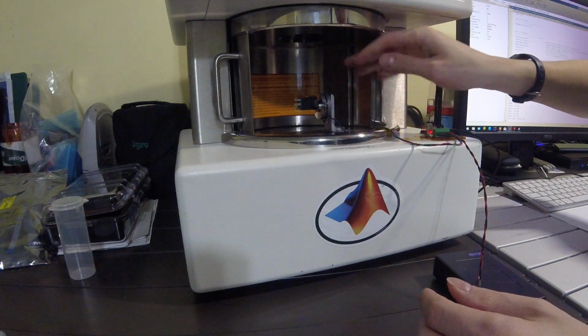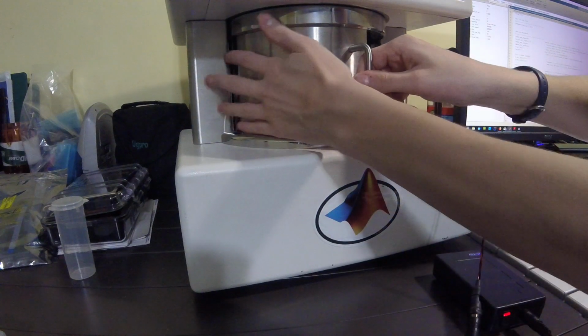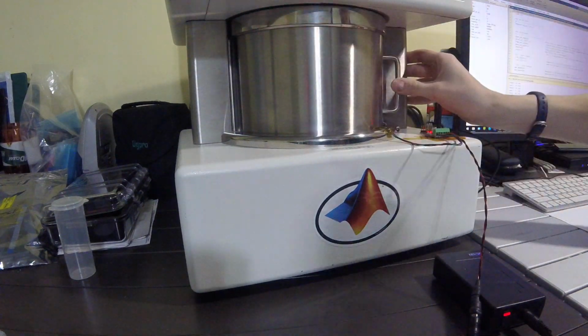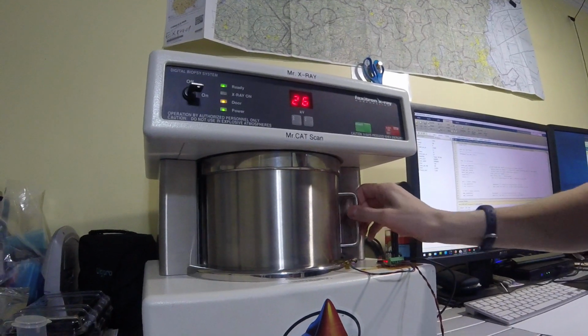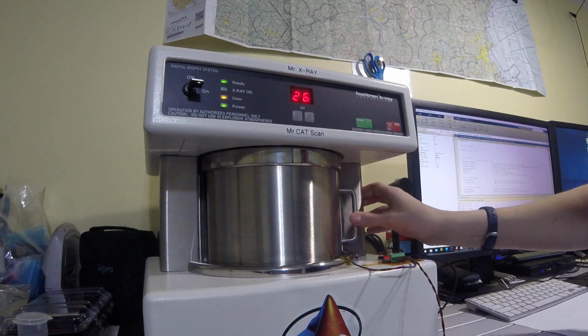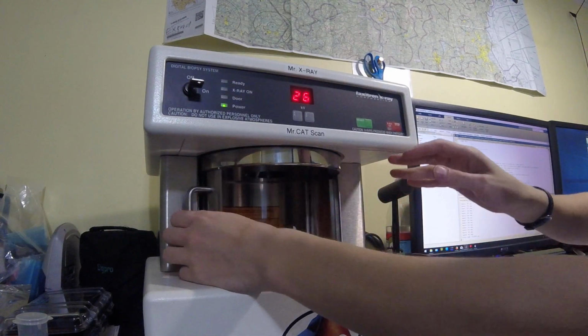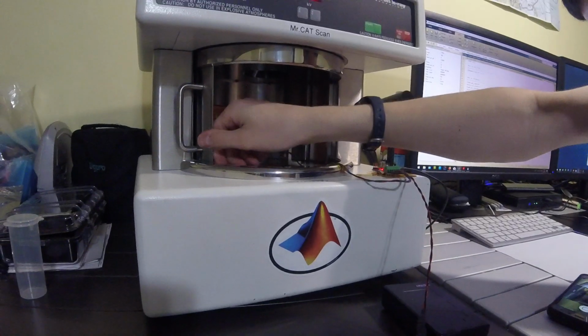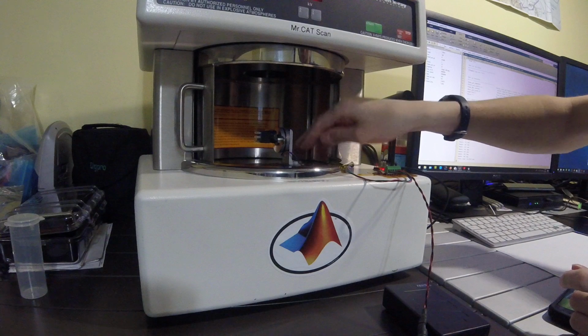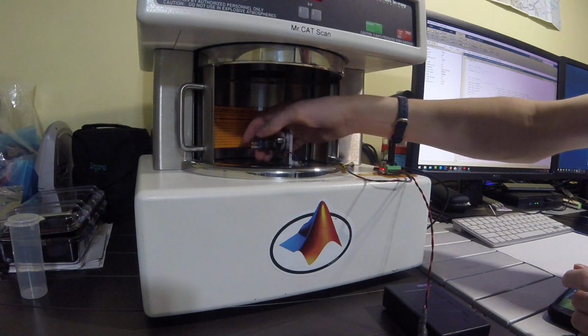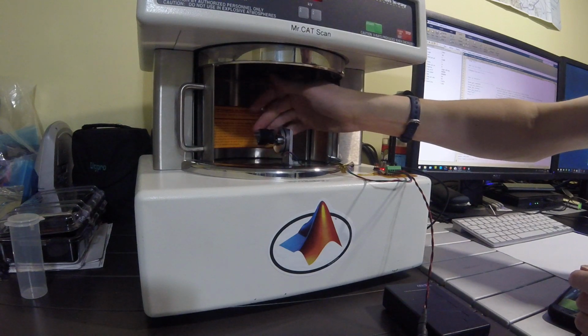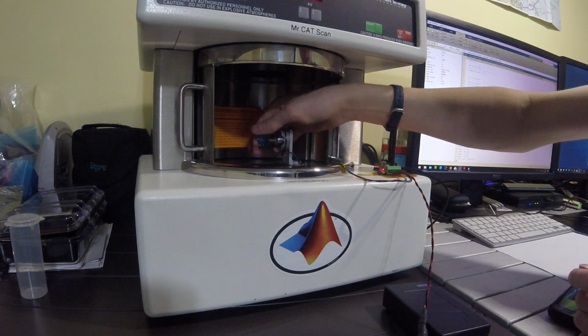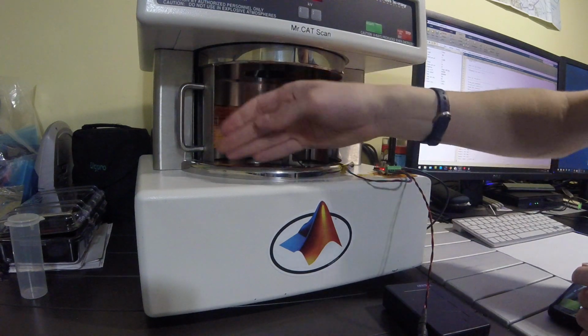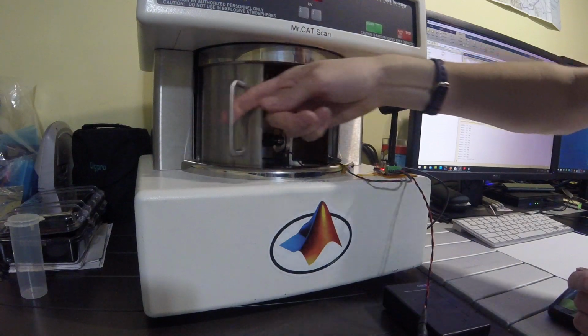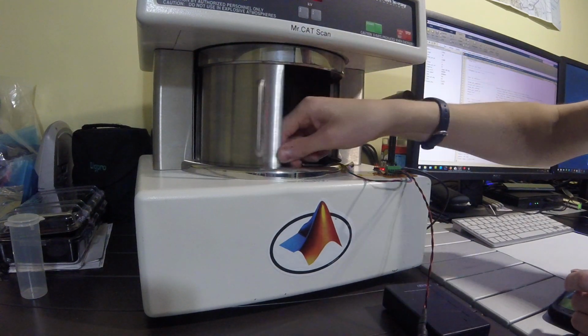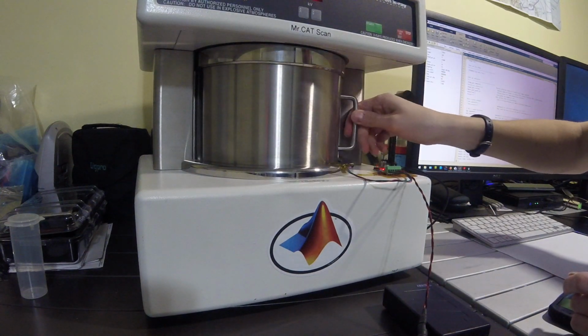around the labyrinth seal. So with the X-ray shield, it has an X-ray shielding door, and of course it has a door interlock, so it will not activate the X-ray generator unless the door is closed. Of course, that should never be bypassed for safety reasons. And the stepper control is actually mounted on a right angle bracket here. And there's a part of a switch, which is just mounted over the X-ray detector, which it can rotate. And the wires, because this is a re-entrant seal, basically just has a U-shaped channel for the shield to move in. The wires are actually thin enough to just snake under that shield.